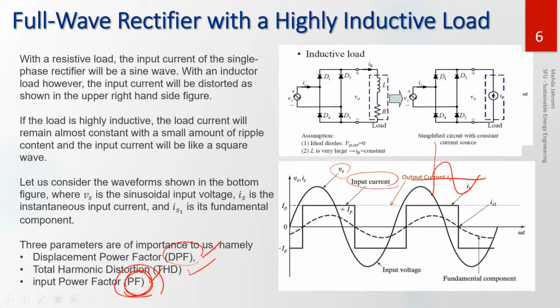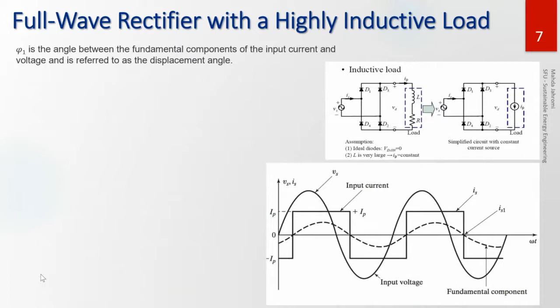The power factor is something that includes the harmonic component. So if your current or voltage is not a perfect sine wave, your power factor should be modified so that it includes the harmonic component as well. I'm going to show you what each one of these terms means.